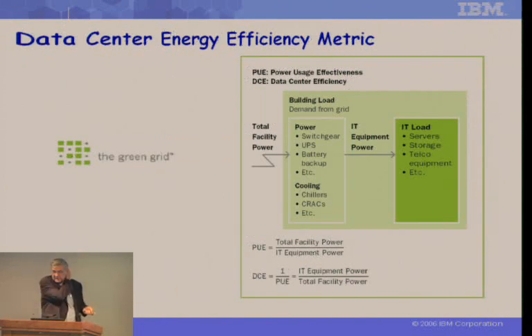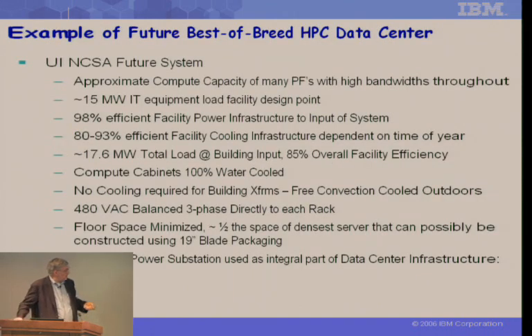I want to mention PUE, power usage effectiveness, which has become somewhat of a standard in industry. It was coined by the Green Grid a couple of years ago. Very simply, it's total facility power divided by IT power. For this data center, that's about 15 megawatts of IT load, and looking at everything, we calculated about 17.6 megawatts in, which works out to about a 1.18 PUE.